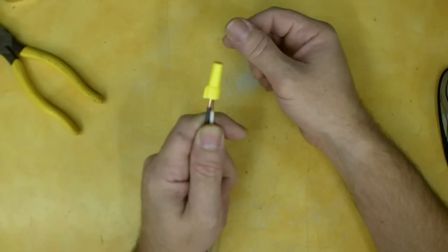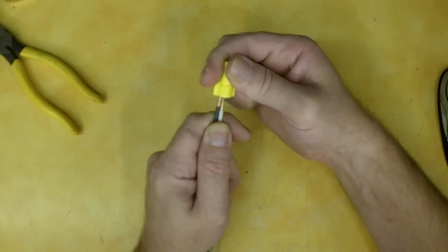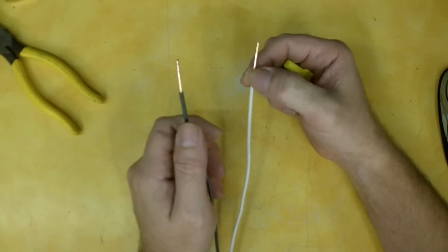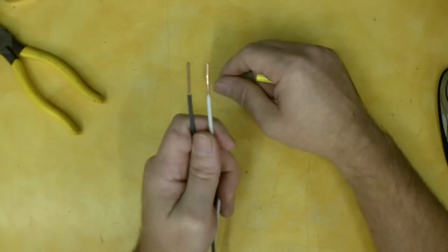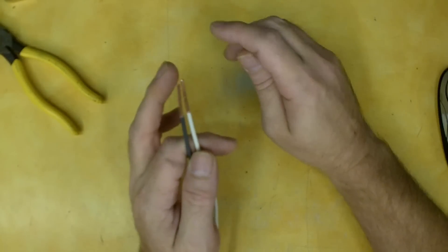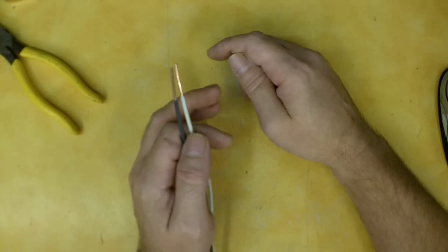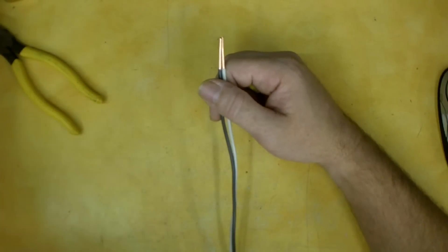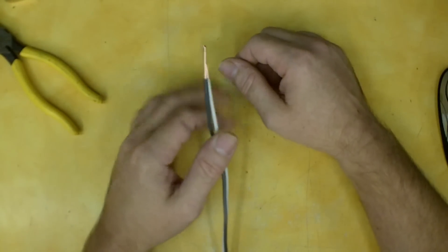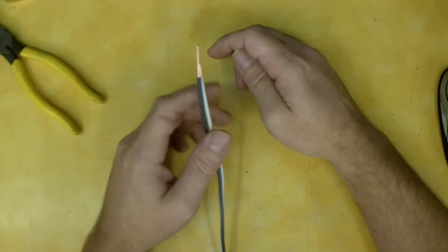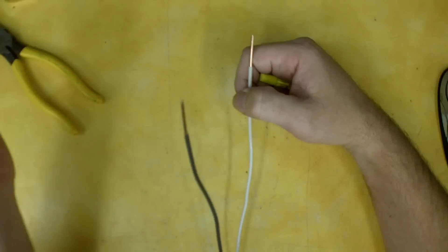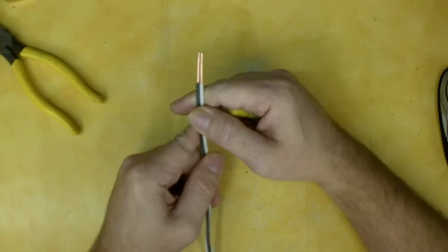These things are going to come loose in time. The nut will loosen up, can potentially get off, and then this is going to come apart inside your junction box, or wherever it's put together. If you are an electrician or have been an electrician, like I have been in one of my past many lives, you'll know if you're working something hot. Like I said, a lot of people work hot. You open something like this up and it flies apart on you and it starts arcing everywhere and snapping breakers or whatnot, you'll hunt down the guy who did that. You will.